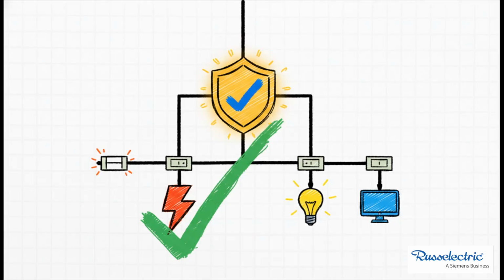And that right there is the winning play. The 30-cycle switch stands firm, holding that line long enough for the smaller breaker closest to the problem to trip. The race is over. The correct breaker wins every single time. The fault gets perfectly isolated, and the rest of the system doesn't even blink.